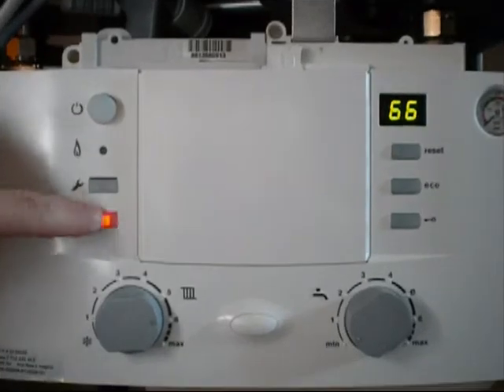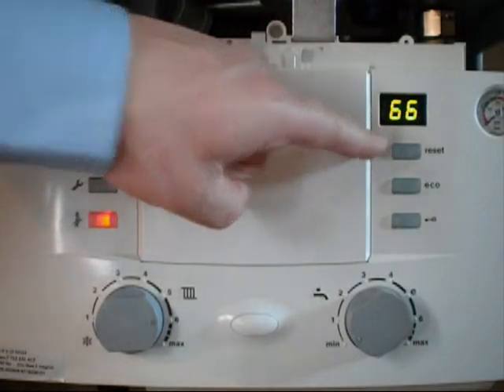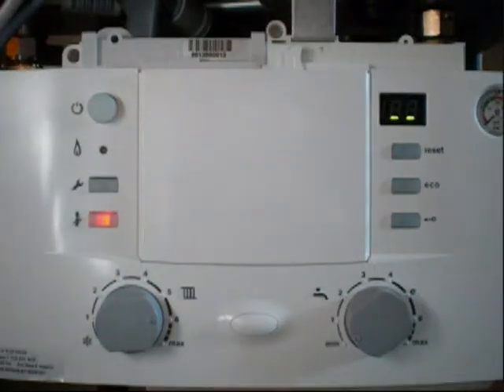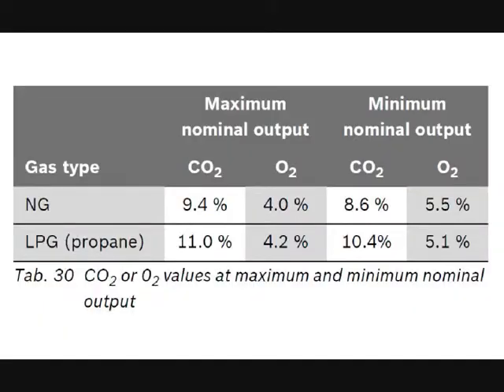To perform the low fire CO2 test, press the chimney sweep button again. The temperature and 2 bars will alternate on the display. 2 bars indicate that the burner is firing at its minimum nominal output. Allow the readings on your combustion analyzer to stabilize. For natural gas, the low fire combustion CO2 reading should be 8.6% as shown in Table 30 on page 77 of the install manual.